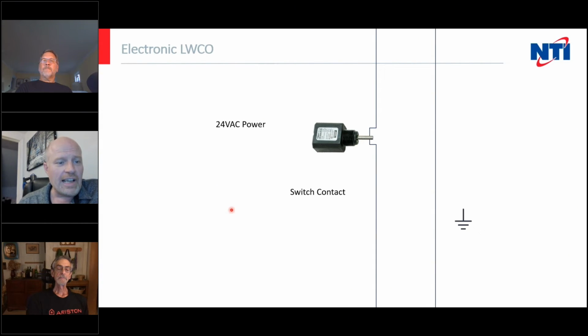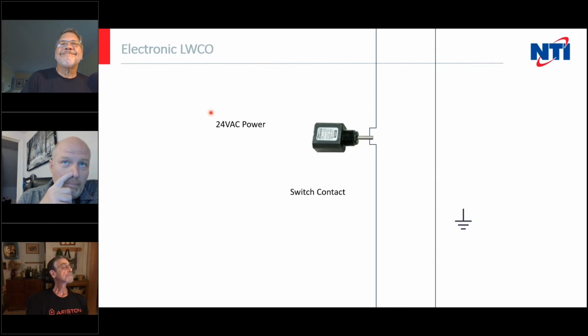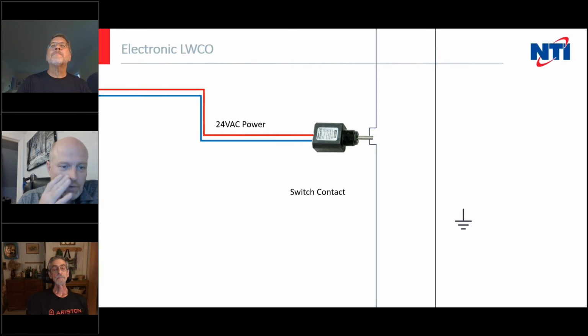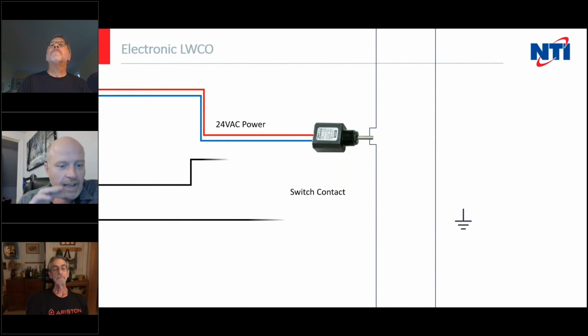So next up here, we've got an electronic low water cutoff. I've chosen the one that goes in the NTI boiler because we're NTI and that's what we're training tonight. If you have a Guard Dog or something, it may run off of 110 volt power, but the concept is the same. So with ours, we've got a blue and a red, which supplies voltage to drive the machine and allow it to work the electronics inside.